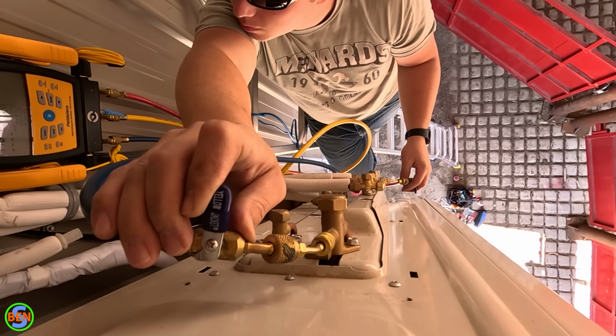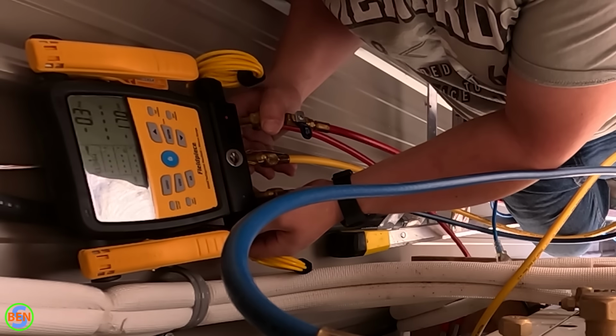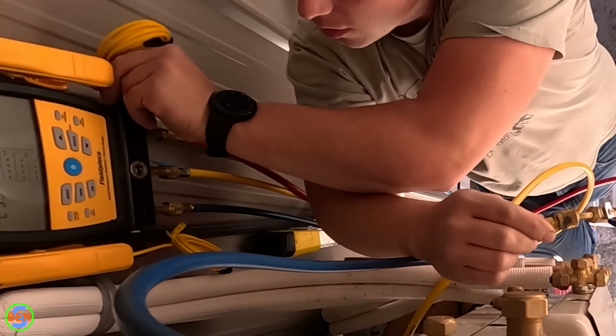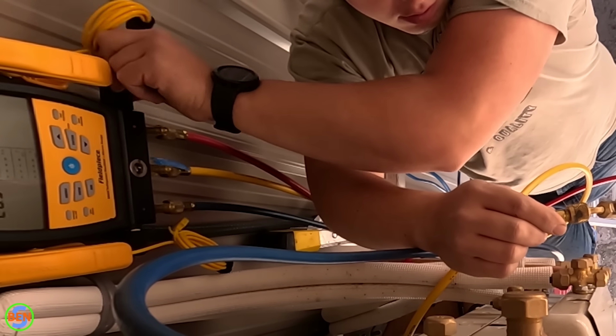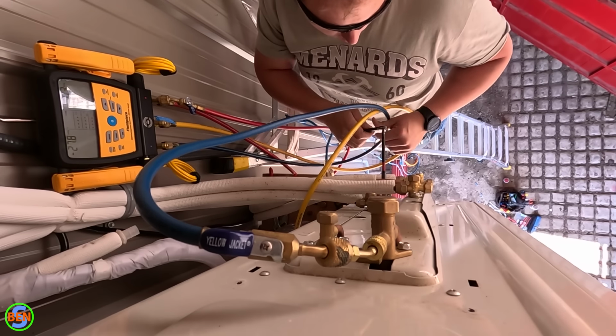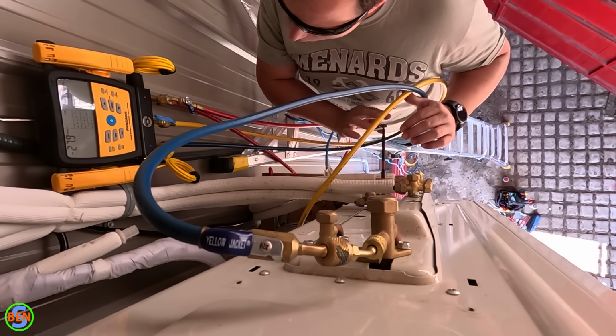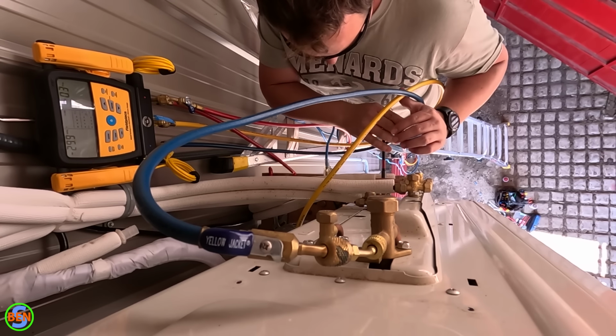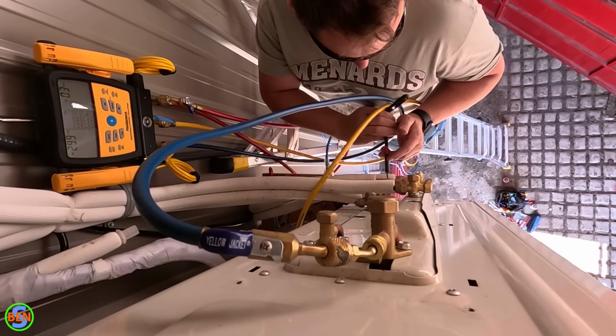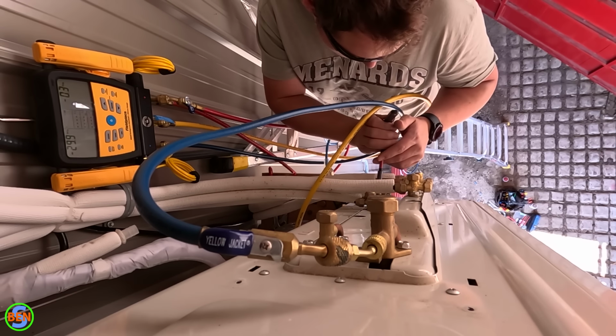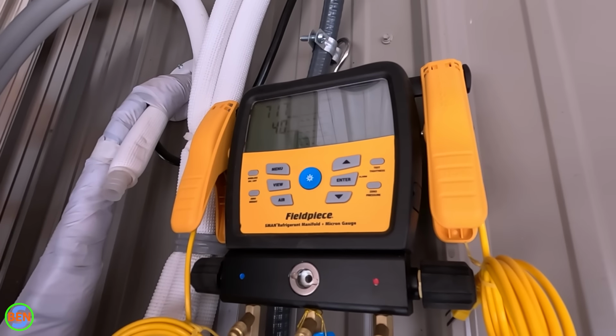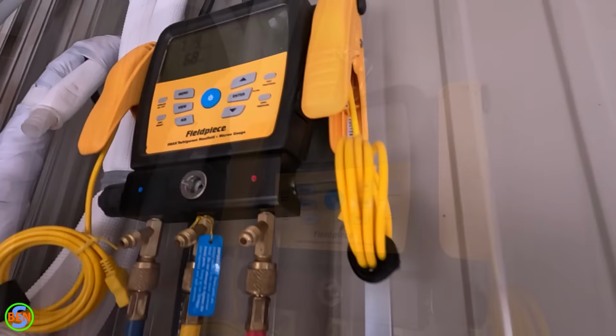So once the vacuum pump is running, you open up both the high side and the low side valves on your gauges, and it'll begin pulling the vacuum down. As the vacuum gets lower and lower, you'll notice that the sound of the vacuum pump will oftentimes change, and it goes from a louder sound usually to being a little bit quieter as all the air has been removed from the system. In my opinion, you want to let this vacuum pump run for at least a half an hour, but it's fine if you let it run even longer than that. Up to an hour would be totally fine by me.